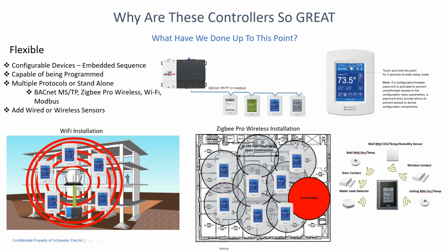As I mentioned before, they're configurable devices. They've got an embedded sequence of operations in them. If you want, you can use the Lua programming to change the standard sequence of operations to fit your piece of equipment. So they're capable of being programmed, or you can use them as just standard configurable type devices. As I mentioned before, there's multiple protocols, or you can do a standalone type device. So you can use BACnet MSTP, which is built in, or Modbus. You can toggle between the two. You can have the Zigbee Pro wireless functionality built into it. So you can get one device that has the Zigbee radio on it, or you can get it without the Zigbee radio and add Zigbee communications to it. Or you can add Wi-Fi communications.